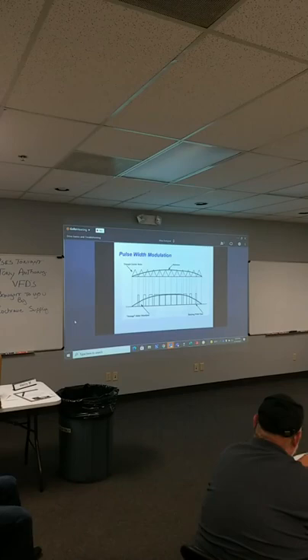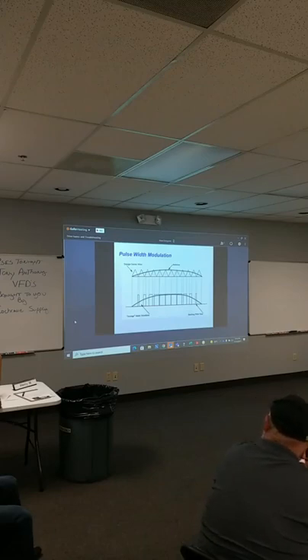And that creates a lot of extra heat. That is why it's so important to make sure that motor is inverter rated, especially if you're putting a drive on an old motor. So if you got a customer that says, hey, I've never had a drive on this motor, I want to put the drive on this motor, make sure you have something in writing somewhere where you've recommended they replace that motor.